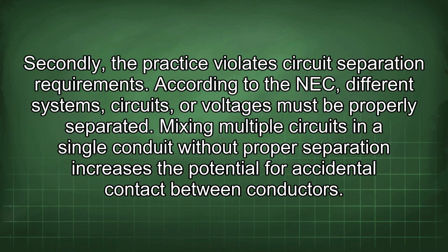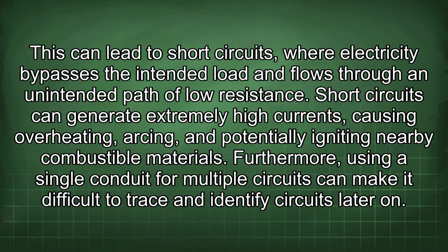Secondly, the practice violates circuit separation requirements. According to the NEC, different systems, circuits, or voltages must be properly separated. Mixing multiple circuits in a single conduit without proper separation increases the potential for accidental contact between conductors. This can lead to short circuits, where electricity bypasses the intended load and flows through an unintended path of low resistance. Short circuits can generate extremely high currents, causing overheating, arcing, and potentially igniting nearby combustible materials.